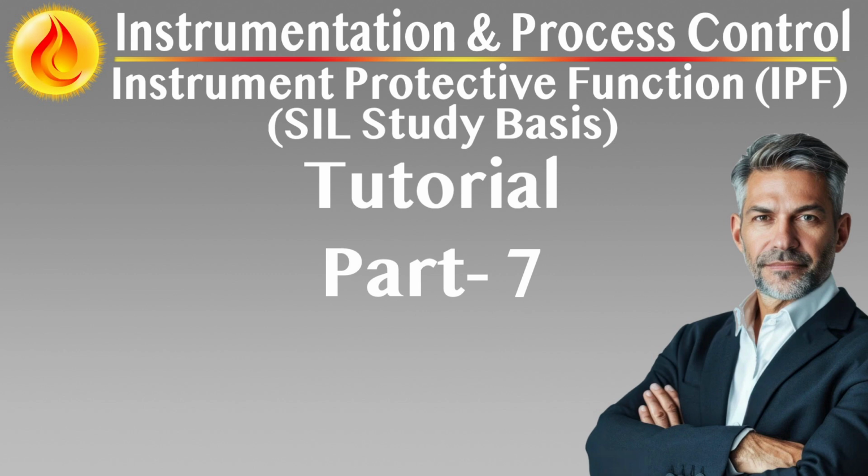Resilience and fail-safe behavior. Override indicators must survive HMI reboot or failover. Any HMI redundancy or failure recovery must preserve and restore the current override status to avoid loss of visibility. Ensure HMI startup screens clearly reflect any IPFs that remain overridden.